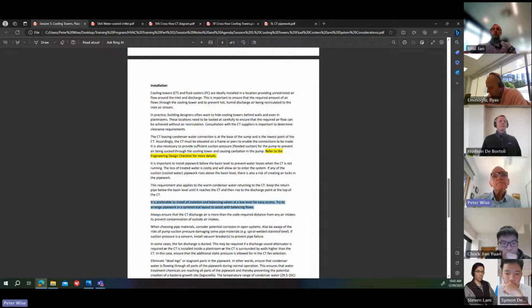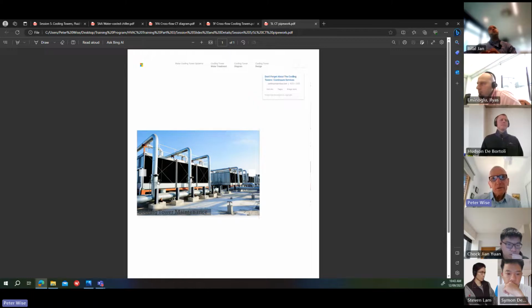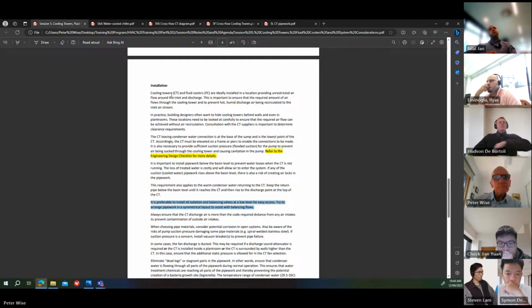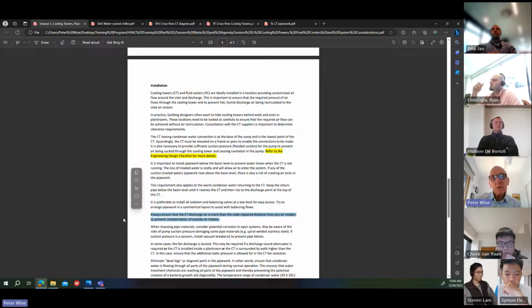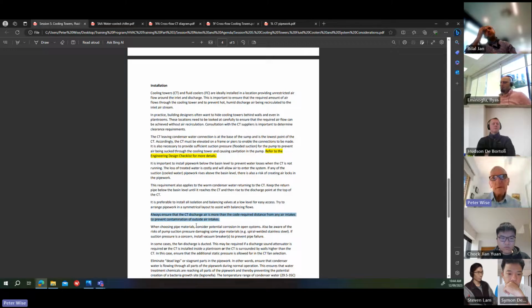So once again, looking at this diagram, you can see these valves are at a low level, so a person can stand there and adjust the valves. It's better being down there than up the top where it's difficult to get to them. Now, there are code requirements for cooling tower discharges, so ensure that you've complied with that, and obviously to prevent contamination of outside air intakes.